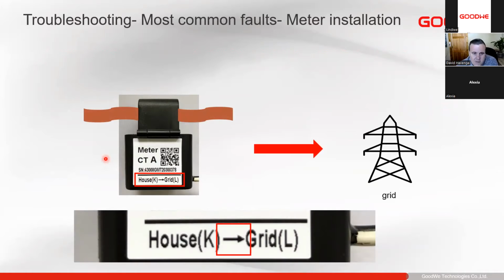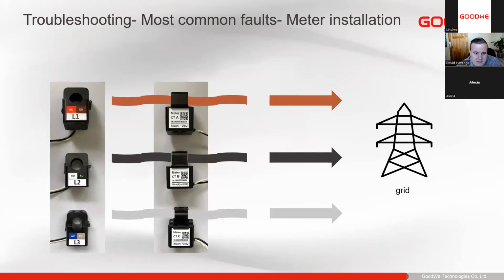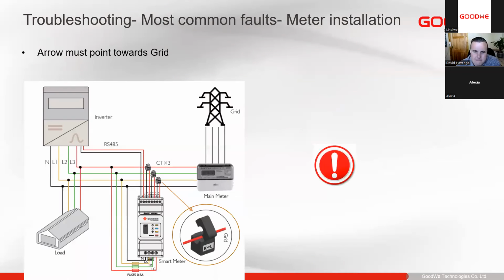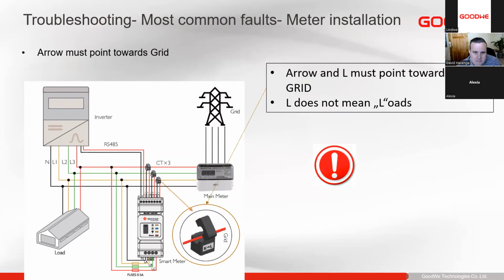The next, as you'll see on all of our CTs, we have an arrow which says K to L. So L is not load. Some people confused L with load. So it's house to grid. So the arrow must always be pointing towards the utility supply, not towards the loads. And in all my years, I've never had a sticker incorrect. So please pay attention, the stickers should always be correct. You'll see it's the same for our three phase. It's just repetitive, rinse and repeat. As you'll see, we reference this over and over again, because it is very important to remember it's always K to L. The arrow points towards the grid from K to L.